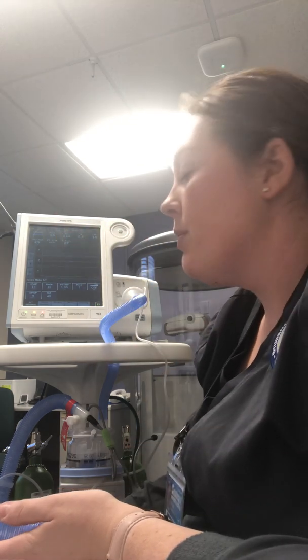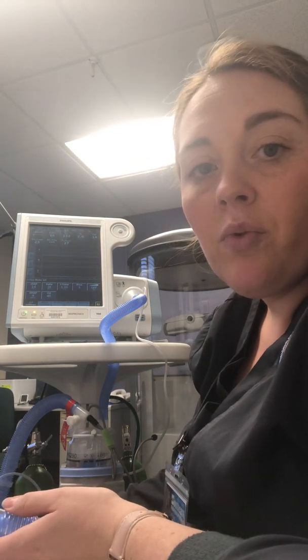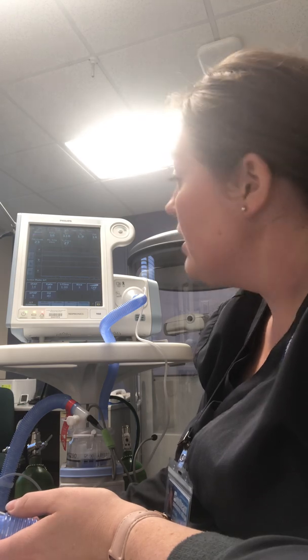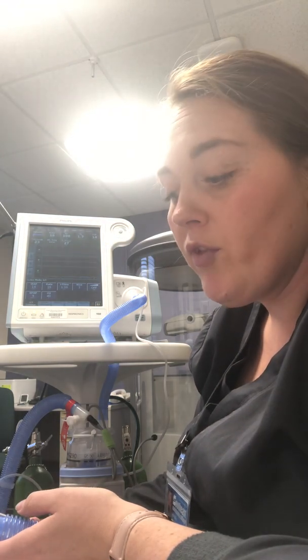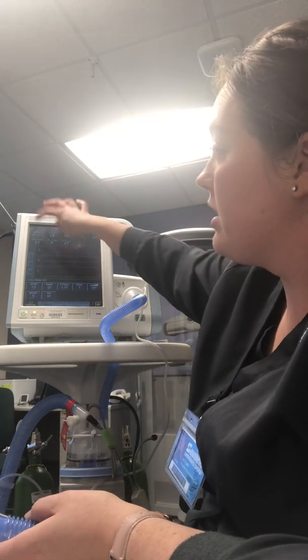We have our IPAP. Normal IPAP is 8 to 20 centimeters of water pressure. We also have our respiratory rate, which is between 8 and 12 to 20 breaths per minute. Our inspiratory time should be between 0.8 and 1.2 seconds. We also have a rise time. Our ramp you can use for patient comfort. That determines how fast your patient's going to get to their IPAP. EPAP should usually be between 4 and 15 centimeters of water pressure, and there should be a pressure support of at least 4 between your IPAP and EPAP. And then you have your oxygen level. So you can set the FiO2 anywhere between 21%, which is room air, or 100% full oxygen.